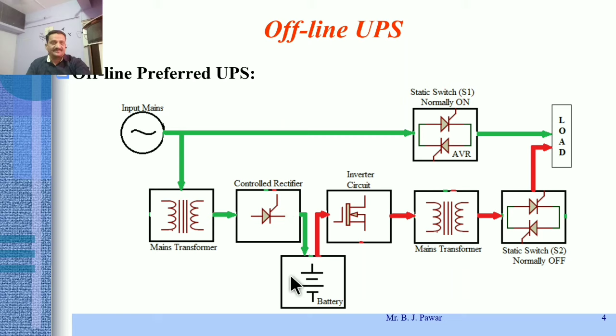So the next type is the offline interactive type. Now see, in the offline interactive type you will observe again there is an AVR, automatic voltage regulator, to regulate the supply voltage to proper values in terms of voltage, frequency, etc. It is connected again to the static switch S1, which is normally on, and that static switch S1 will power the critical load through the line conditioners. Line conditioner means what? Again it will maintain the supply conditions in terms of its harmonic content, then deviation in frequency, deviation in amplitude, etc.